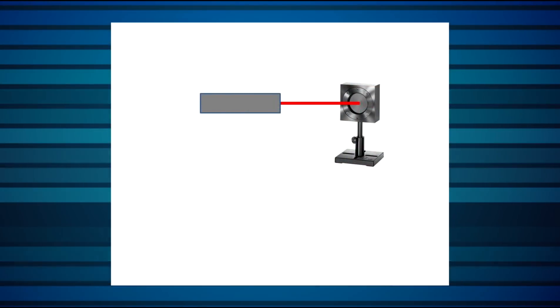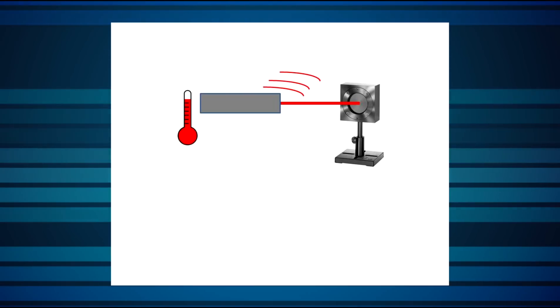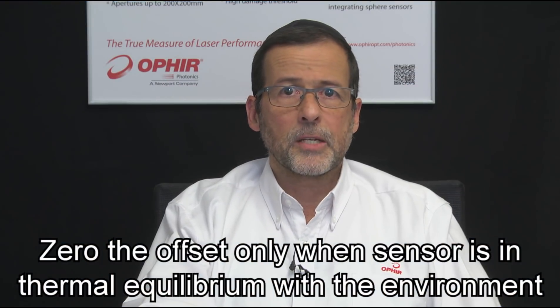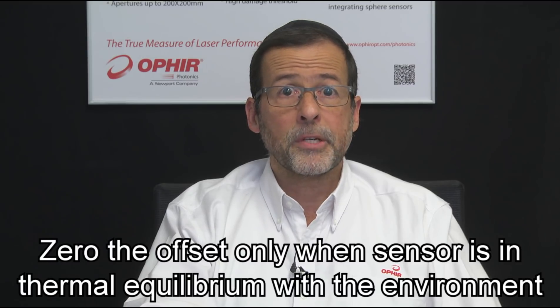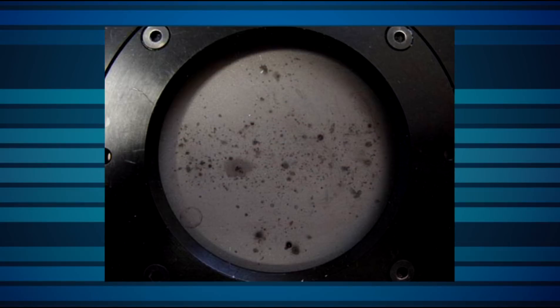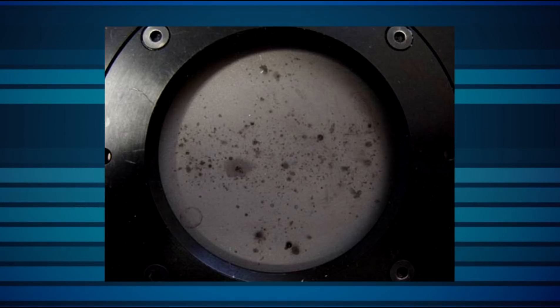For thermal sensors, check that the environment is thermally stable. A temperature change of even 1 degree Celsius per minute can be picked up by a thermal sensor — it's that sensitive — and cause heat flow that would be misinterpreted by the sensor as incoming laser power. Check that there's no nearby heat source causing any thermal offset; that might even be the light source itself. Zero the sensor offset only when the sensor is in thermal equilibrium with its environment. Otherwise, you might be zeroing out an offset that will soon change, and continuing to subtract its value from readings would then introduce an error. Be sure the sensor is clean — trivial perhaps, but worth checking just in case.